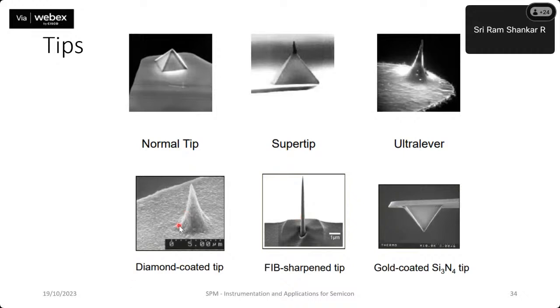Based on the hardness of the sample, you can also go for a diamond-coated tip, where you grow diamond on the tip so that the entire tip becomes very hard, making it resistant to tip wear. Over repeated scan motion, the tip gets blunt, and a diamond-coated tip would avoid or minimize that.